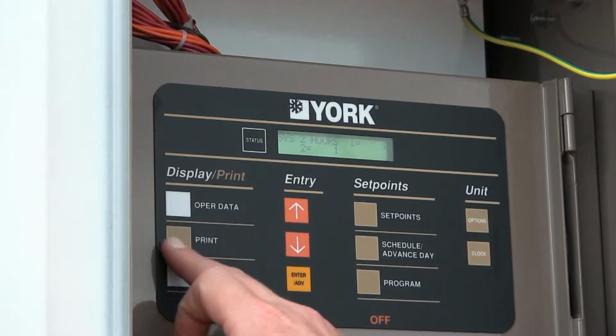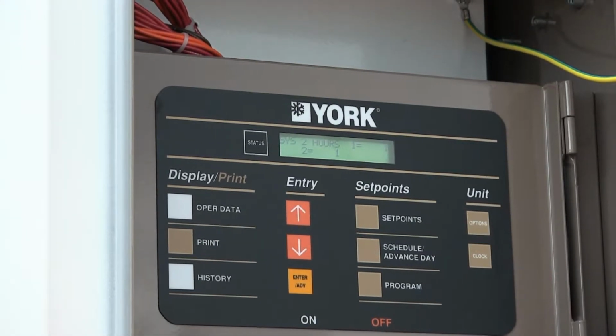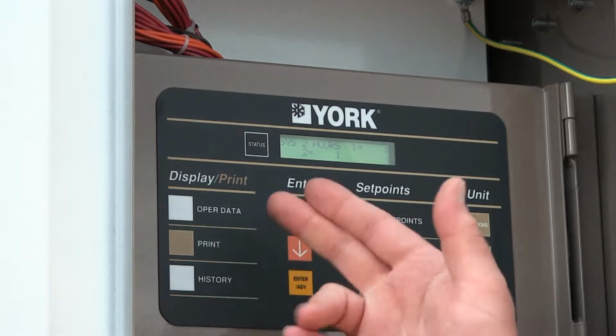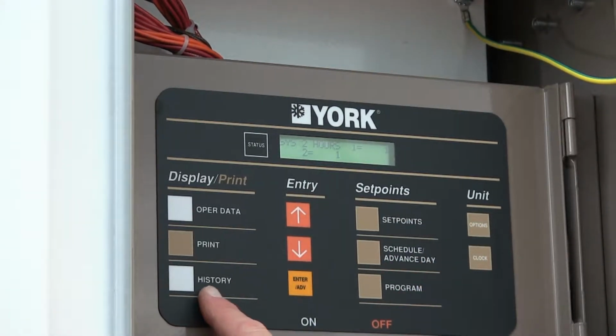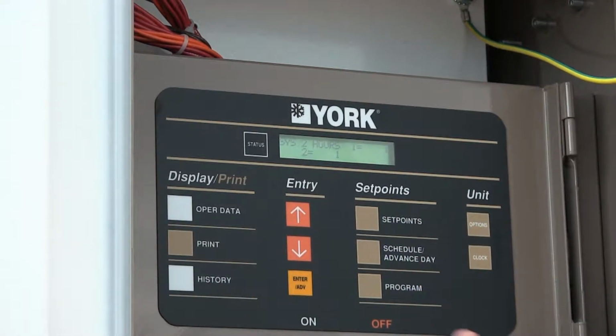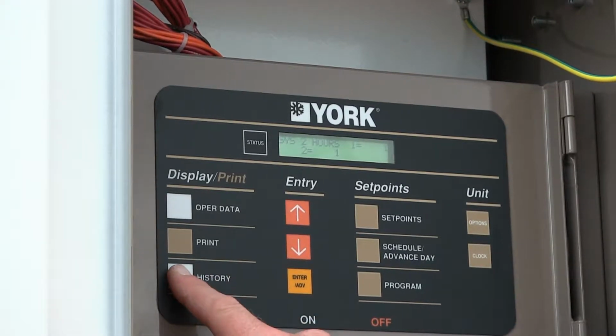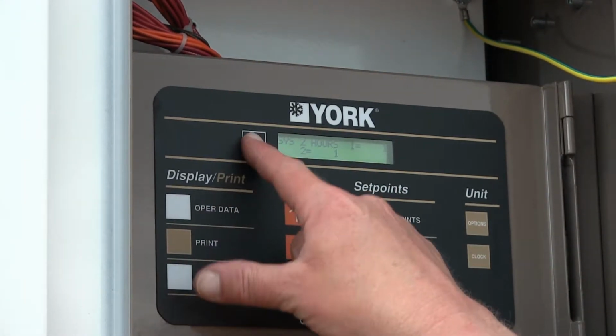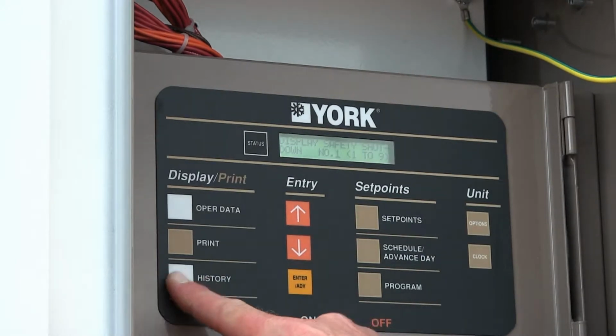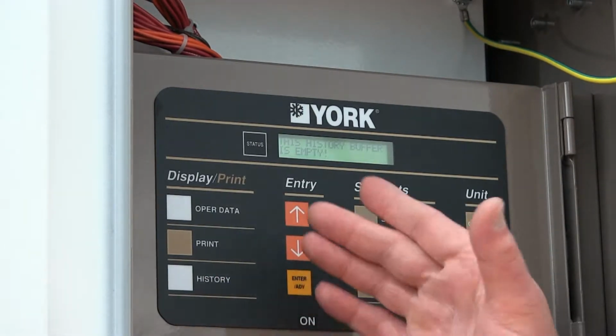The next button is print. The print button is if you want to plug in a printer to the microprocessor and print an alarm history. The next button is a history button, which anytime you have a fault, you push the history button. We'll go to status, back to status. We'll go to the history button, it'll do a safety shutdown. It'll tell you that there's an alarm.